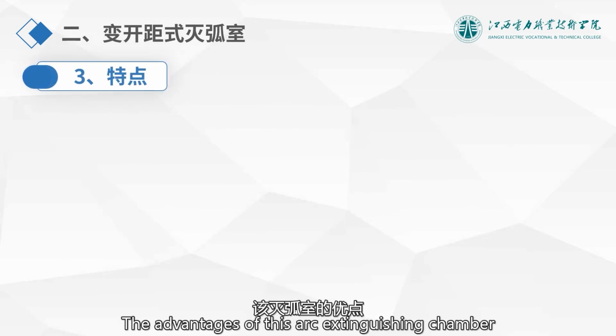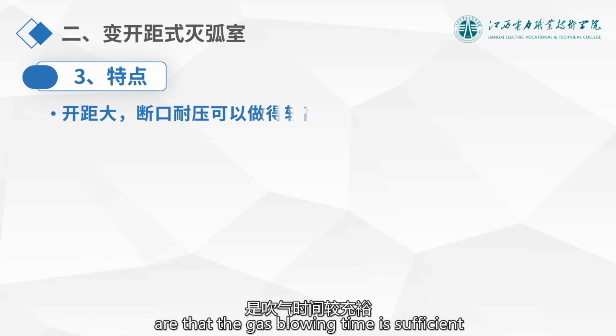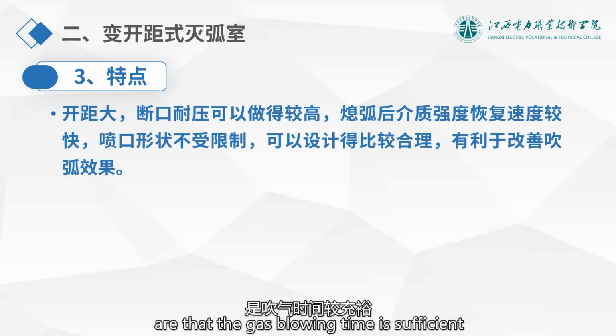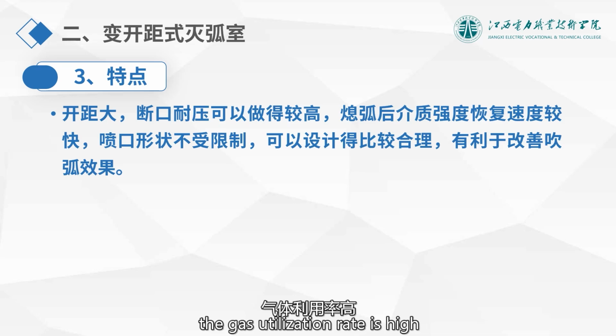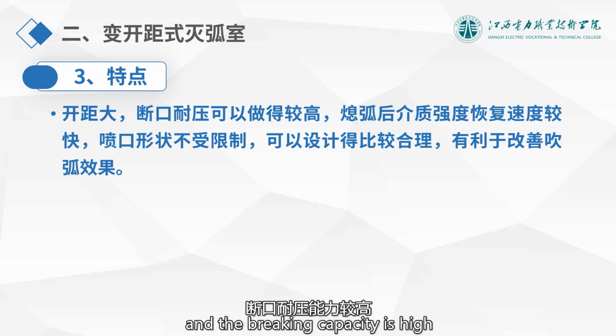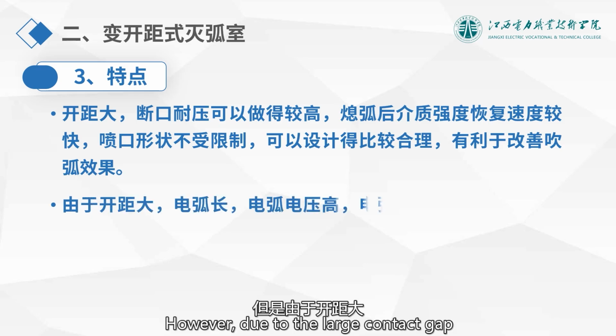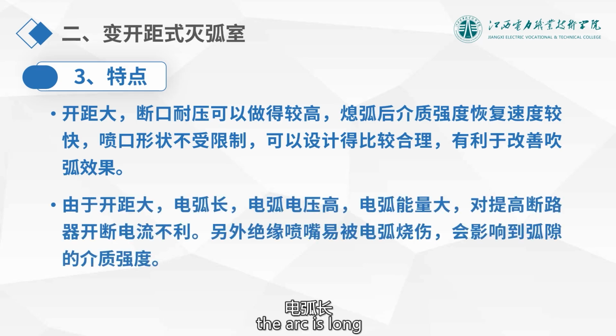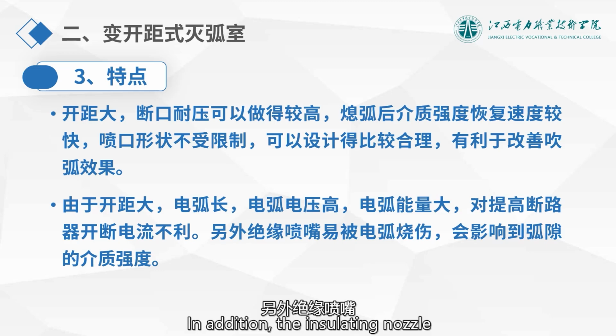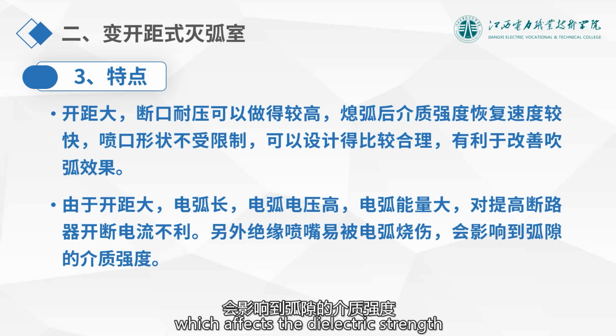The advantages of this arc extinguishing chamber are that the gas blowing time is sufficient, the gas utilization rate is high, and the breaking capacity is high. However, due to the large contact gap, the arc is long, the arc voltage is high, and the arc energy is large, which is not conducive to increasing the breaking current of the circuit breaker. In addition, the insulating nozzle is easily burned by the arc, which affects the dielectric strength of the arc gap.